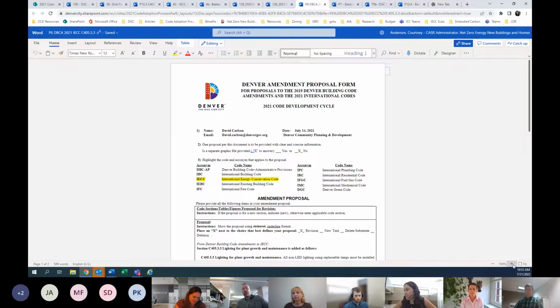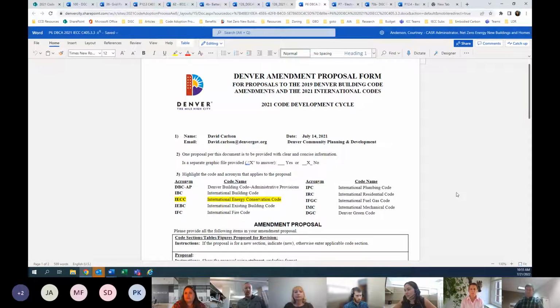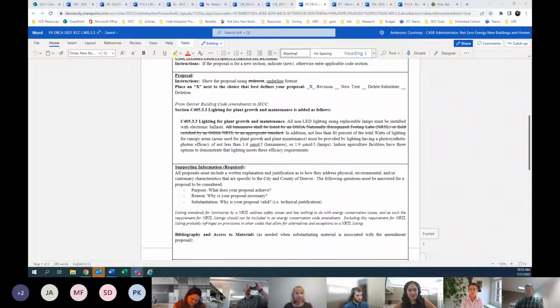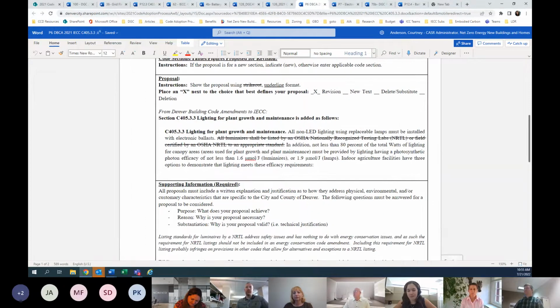David Carlson, thank you for joining us today. I'm sorry we only gave you 5 minutes, but hopefully we can get through some of these. Well, the first one is just a housekeeping one. In the lighting for plant growth, there's a reference to require UL listing or nationally recognized testing laboratory listing of luminaires for plant growth. Well, in an energy conservation code, you shouldn't really be referencing a safety item. Those are covered in the respective building codes. I do know the NEC has an article or a paragraph regarding requiring listing of equipment. So I think it should be deleted from here.